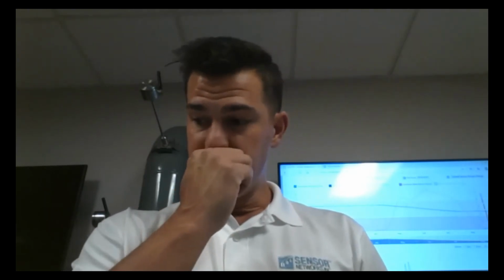Can these be installed at locations where the pipe has a dent or external damage, to monitor future internal corrosion? Maybe - the sensor has to sit flat, or on a relatively flat surface. If you can get the sensor to sit on it and give you a good reading, then yes. But if it's too dented and you can't get the sensor to sit flat on the area you're looking to measure, then likely not.